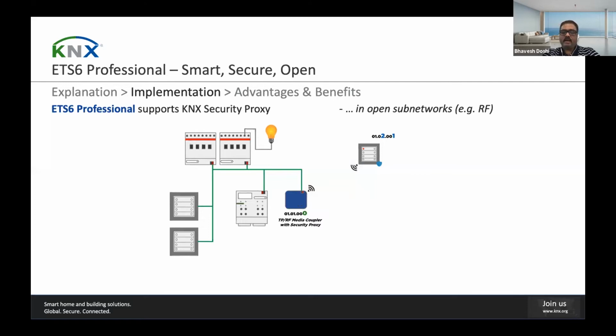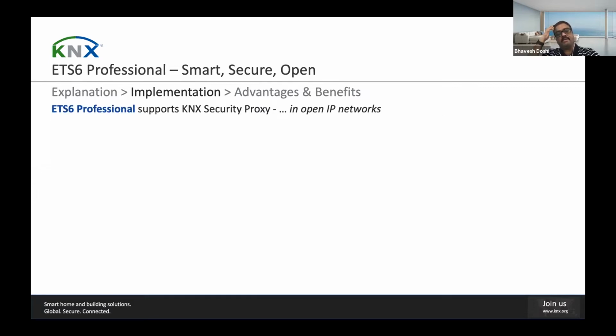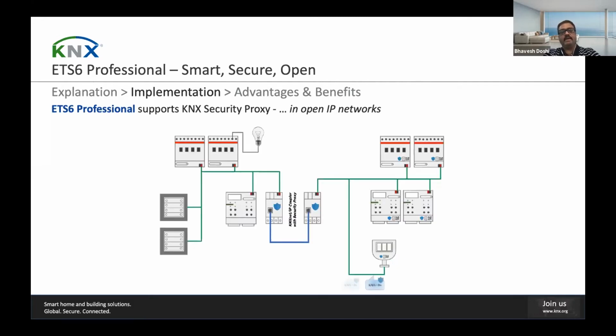But at the same time, allow integration of KNX RF secure devices into applications that are available plain on the KNX twisted pair segment. Example, an additional secured KNX RF push button participating in the same group as a plain KNX twisted pair push button and a plain KNX twisted pair light switch actuator. So to achieve this, the coupler device that separates the secured subnetwork from the plain subnetwork must act as a middleman when routing KNX frames from one subnetwork to the other and transparently add or remove the KNX data security to or from the KNX frame.